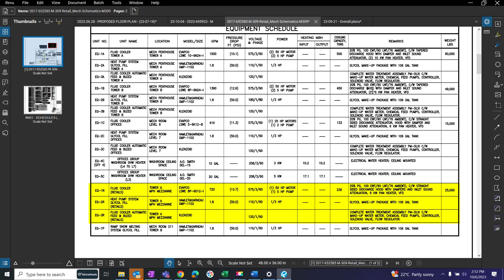What's interesting is the fluid cooler tower numbers look reasonable, because your tower can only cool it to your ambient, and that's 90, which makes sense since your peak ambient in Toronto is probably 90. But an actual fluid cooler device that's pumping and compressing using energy, those are the same values as your fluid cooler up above, aren't they? 100 entering and 90 leaving, same as the fluid cooler on the roof. So I'd suggest those numbers are wrong, because the fluid cooler would be doing nothing then.